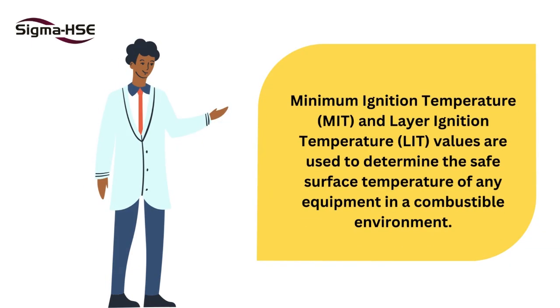Minimum ignition temperature and layer ignition temperature values are used to determine the safe surface temperature of any equipment in a combustible environment.